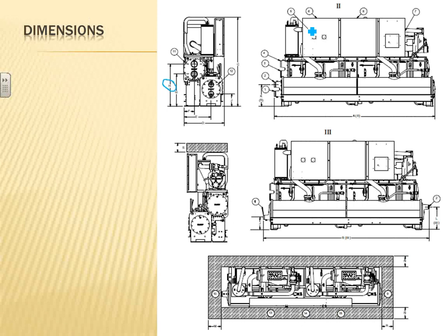The way I would think of it, say if I want to put a switch, electrical switchgear right in here, right? Yeah. And now I need my, let's just say 3 to 4 feet of clearance right in here. So that might be a consideration for us if we are to put our electrical equipment into the mechanical room, to pay attention to the clearances that they need around the electrical equipment. I'm sure there will be a lot of discussion with the mechanical engineers too, but electrically speaking, we only care about electrical equipment, and typically it's 4 feet, 3 to 4 depending on the voltage, but for 480 hot from both sides, it's 4 feet. So you clear 4 feet for yourself, you're good.